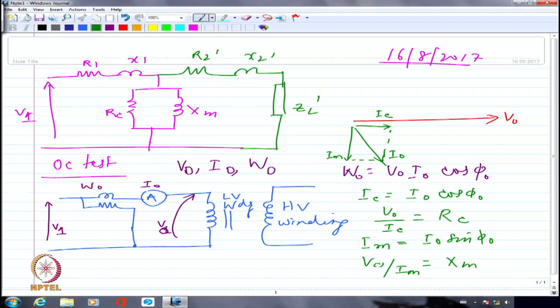I am not loading the transformer. I have kept the secondary on open circuit. That's the reason this is known as the no load test or open circuit test. Incidentally, the same circuit can be used for determining the B-H loop, but with a little bit of modification. So we are looking at the transformer under open circuit condition, with the secondary on open circuit. The primary is applied with the normal magnetizing current because it is on open circuit. Let me put a small resistance in series with the primary winding, which I call RS. So RS multiplied by IM, the magnetizing current or the no load current, will be the drop across the series resistance.